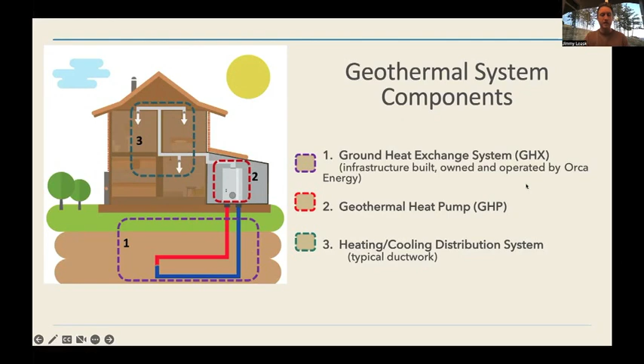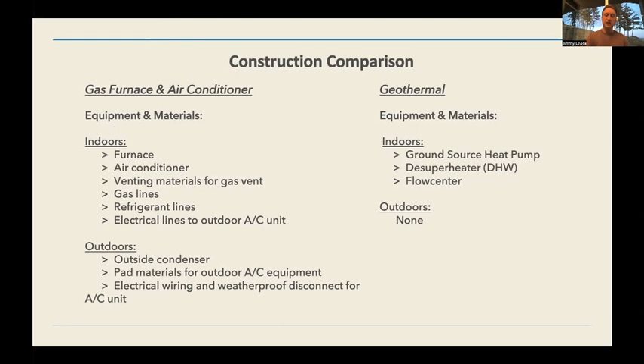With your traditional gas furnace, you're going to have your furnace, your air conditioner, which sits outside, your venting materials, all your gas lines, your refrigerant lines, and your electrical lines that run outdoors to your AC unit. And outside, you will have your condenser, your pad for the outdoor equipment, and your electrical wiring and weatherproof disconnect for the AC unit. Whereas with a geothermal system, inside you just have one ground source heat pump in one box that does your heating and cooling. It does have the ability to put a de-superheater on there, which can supplement your domestic hot water, and a small pump or flow center within your mechanical room that connects the ground loop to the heat pump. And that is it. There is no outdoor equipment. All of the infrastructure is buried underground, which is wonderful. So you get to eliminate a lot of that outdoor nuisance.